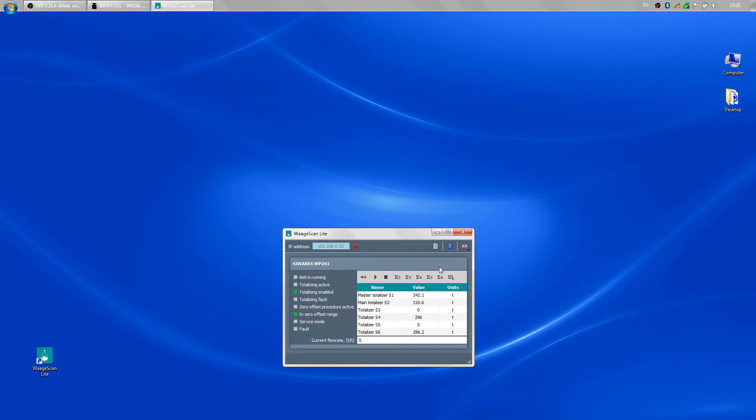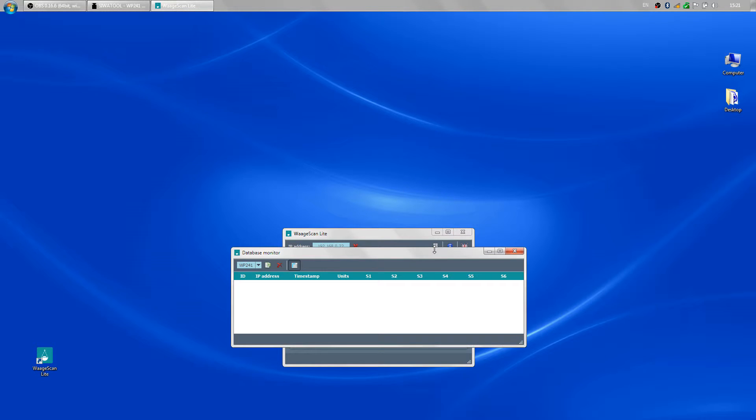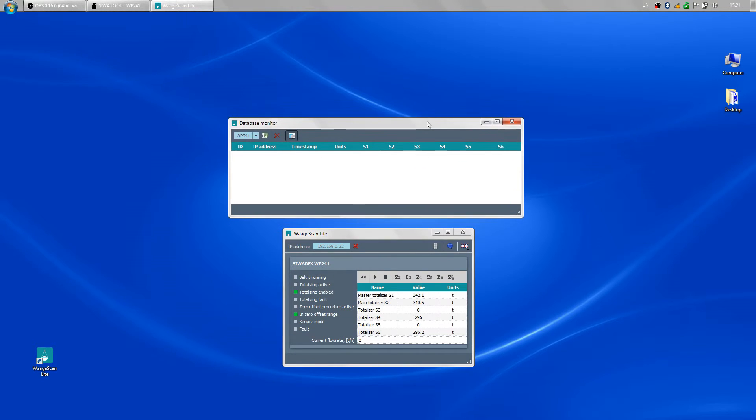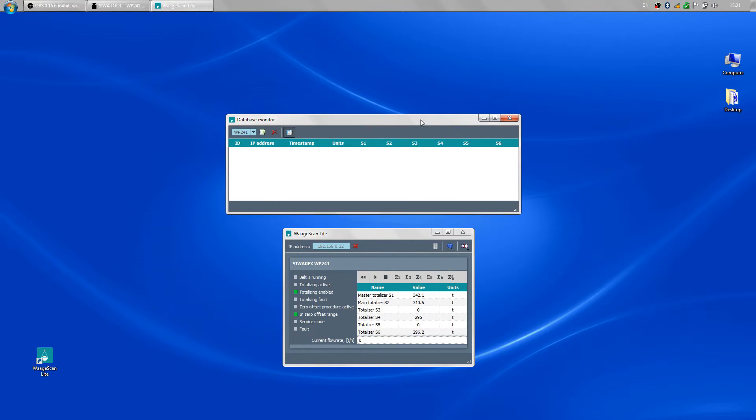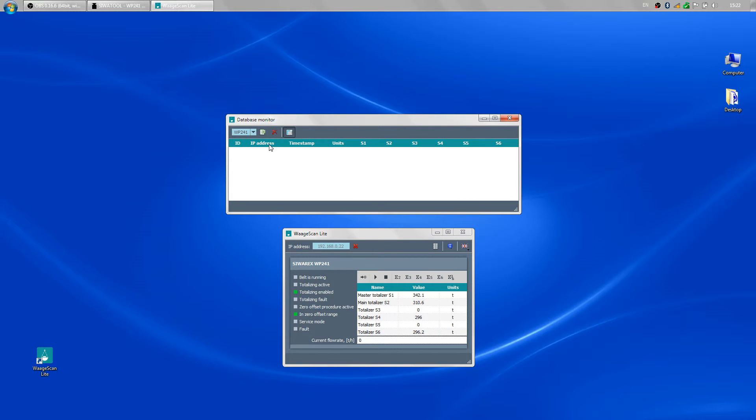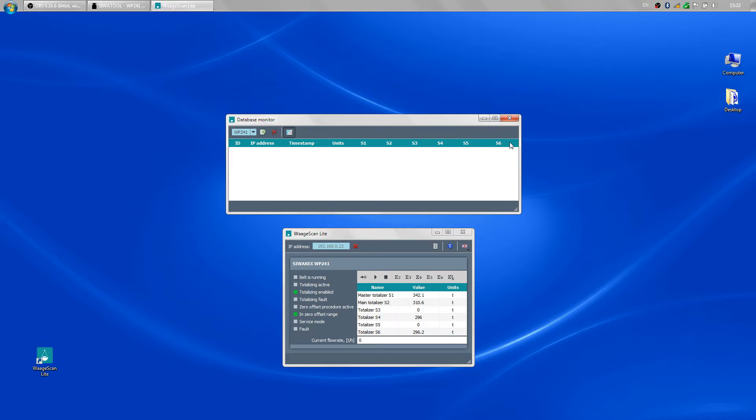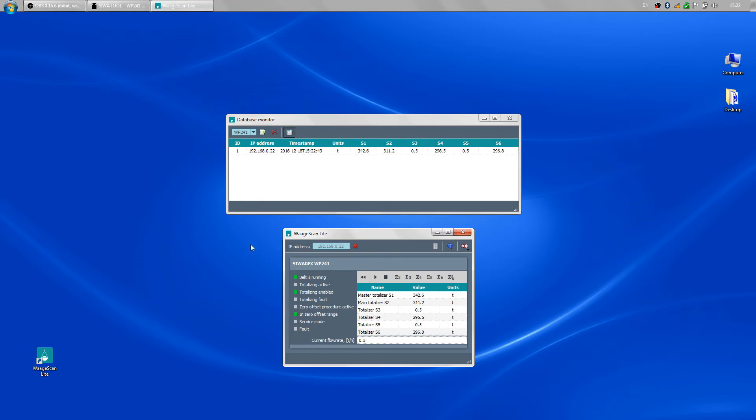To monitor the database, I press F7. The table for WP241 is shown. There are 10 columns: Record ID, IP address, a timestamp, units and the values of the totalizers S1 to S6. Each time the totalizing is deactivated, the current data is recorded in the database.